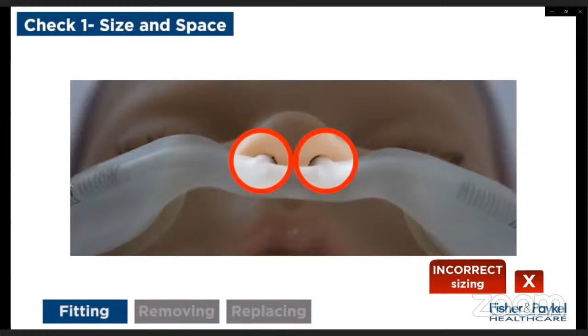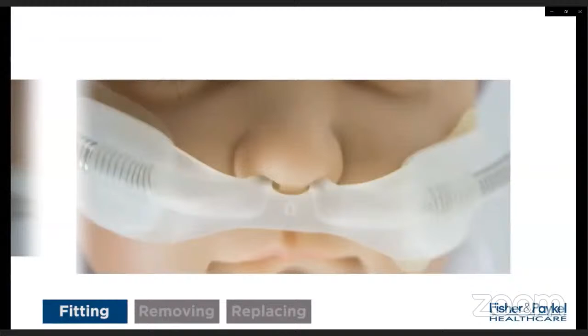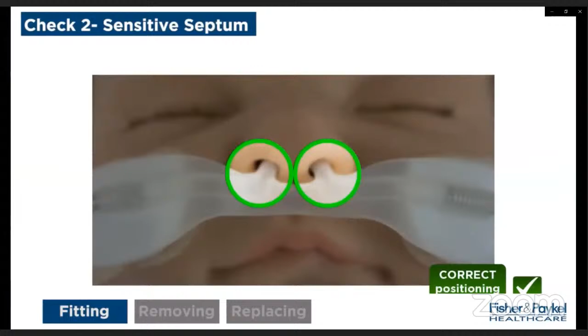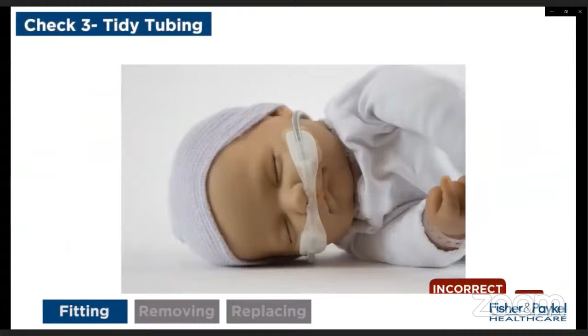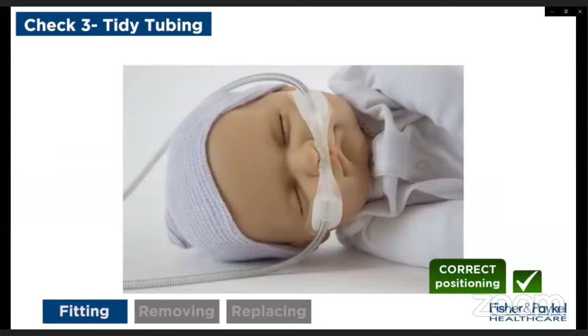Optiflow Junior 2 nasal cannula checks. Ensure the recommended nares occlusion is approximately 50%. Ensure the cannula bridge rests close to the nose without touching the septum. Ensure the patient does not lie on the tubing, as this may apply pressure to the patient's ears or face.